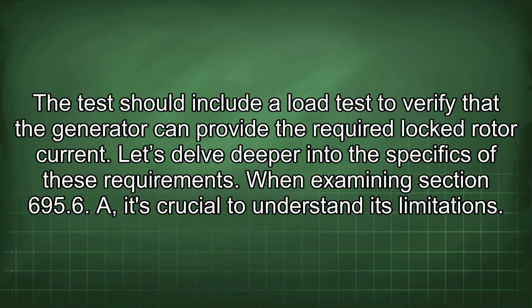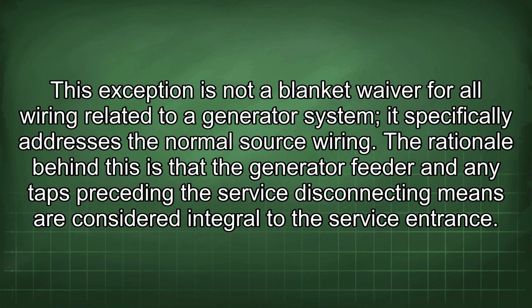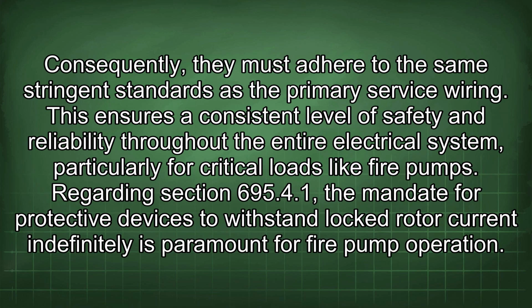Let's delve deeper into the specifics of these requirements. When examining section 695.6, it's crucial to understand its limitations. This exception is not a blanket waiver for all wiring related to a generator system, it specifically addresses the normal source wiring. The rationale behind this is that the generator feeder and any taps preceding the service disconnecting means are considered integral to the service entrance. Consequently, they must adhere to the same stringent standards as the primary service wiring.